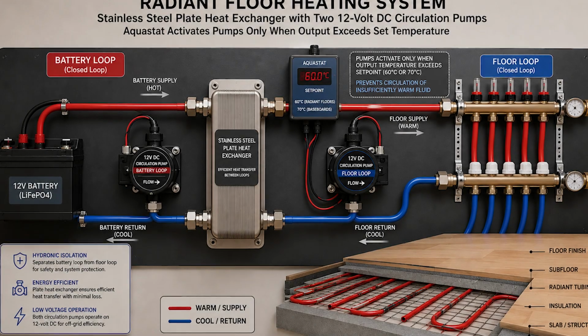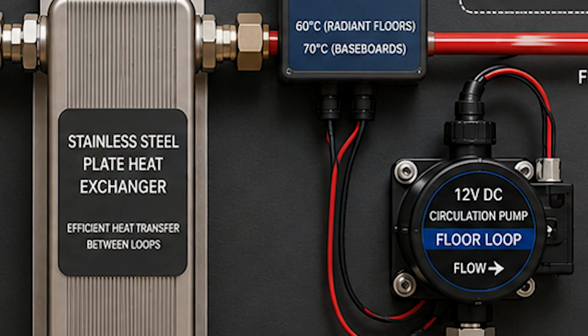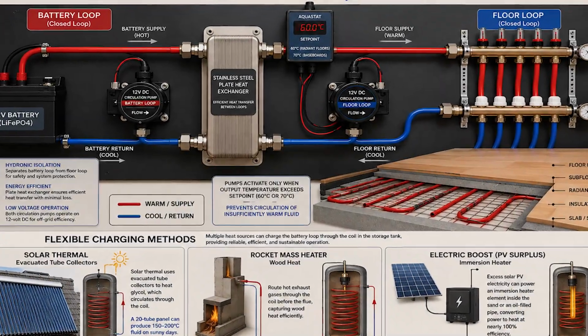Install an Aquastat temperature sensor with relay on the output pipe. Set it to activate pumps only when output exceeds 60 degrees Celsius for radiant floors or 70 degrees Celsius for baseboards. This prevents circulation of insufficiently warm fluid.